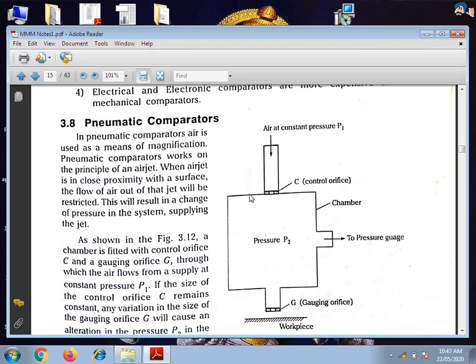Now come to the pneumatic comparators. In pneumatic comparators, air is used for getting the magnification, air is used as a means of magnification. Pneumatic comparators work on the principle of an air jet. When the air jet is in close proximity with a surface, the flow of air out of that jet will be restricted. This results in a change of pressure in the system.